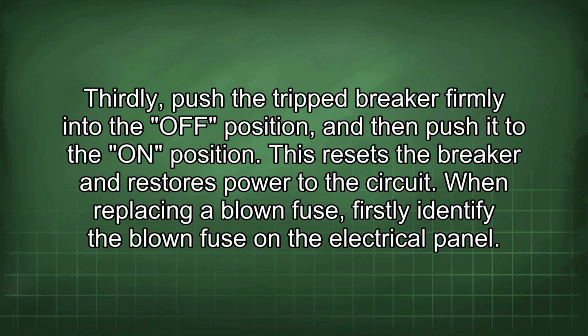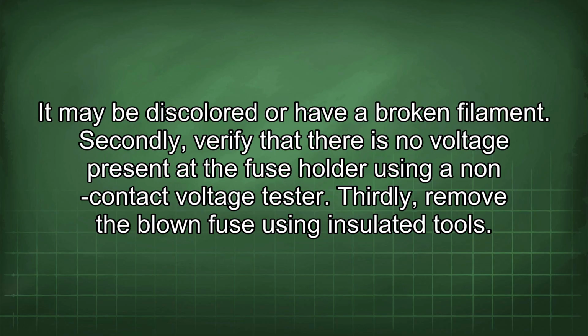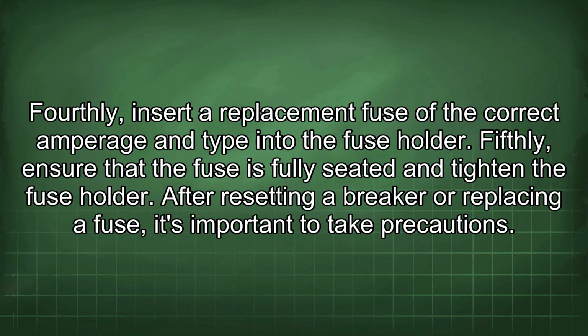When replacing a blown fuse, firstly identify a blown fuse on the electrical panel. It may be discolored or have a broken filament. Secondly, verify that there is no voltage present at the fuse holder using a non-contact voltage tester. Thirdly, remove the blown fuse using insulated tools. Fourthly, insert a replacement fuse of the correct amperage and type into the fuse holder. Fifthly, ensure that the fuse is fully seated and tighten the fuse holder.